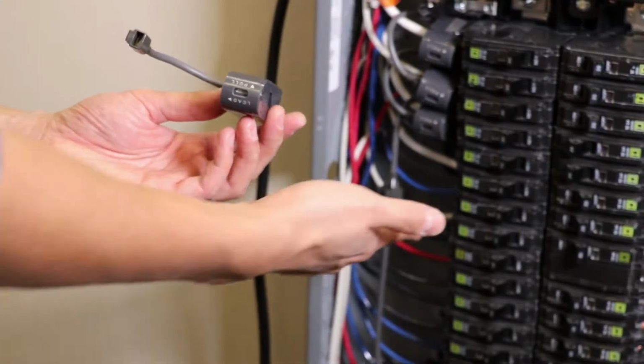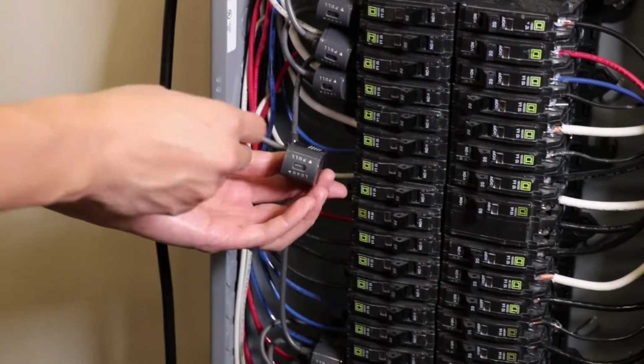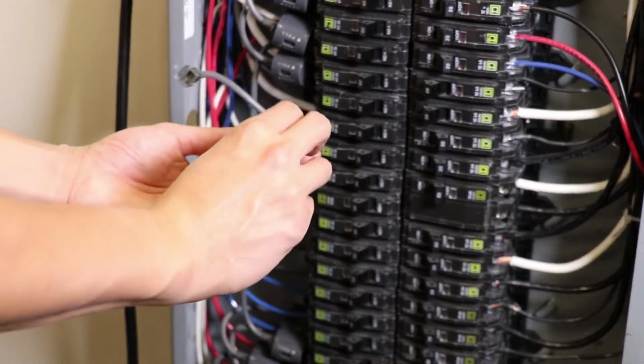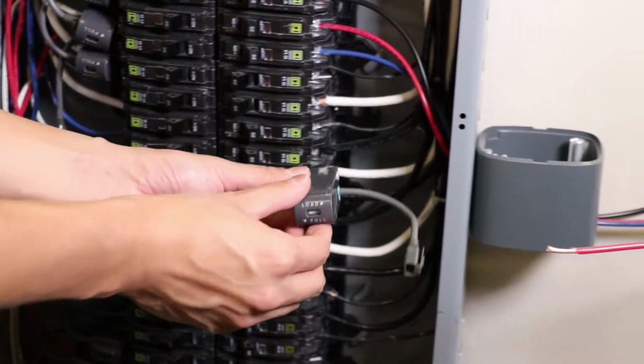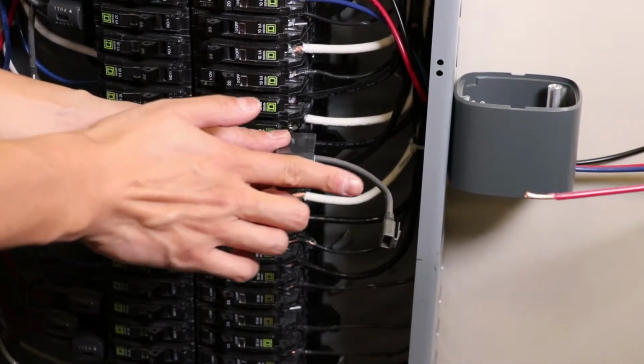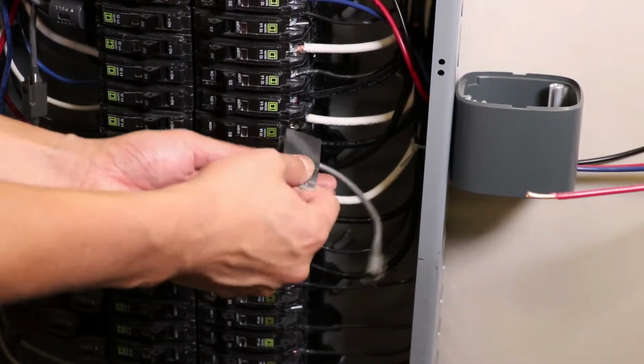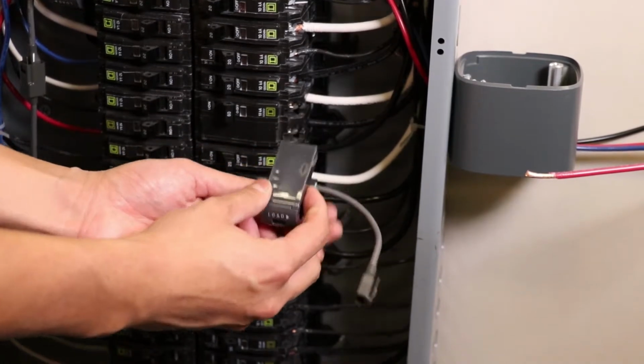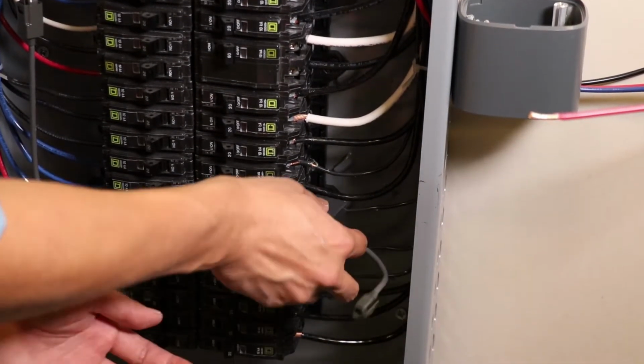When we installed on this side, our load was facing this way, so our wire goes out this way. If we're installing on the other side of the panel, we want our current to still flow in the direction of the load, so we will install our CTs in this direction on this side of the panel.